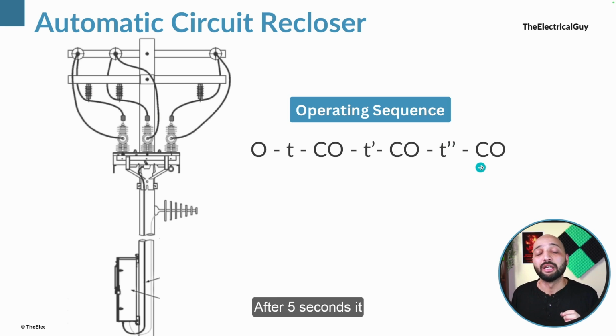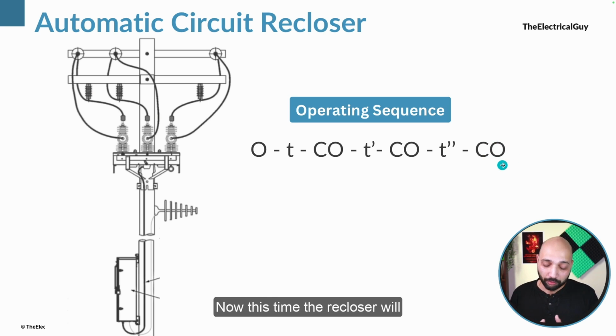After 5 seconds, it will close again. If the fault is clear, it will remain closed. But if not, then it will open again. Now this time the recloser will consider this as a permanent fault and it will remain open. So now you have to go manually and close it. You have to go and manually close the recloser in order to continue the supply, right?